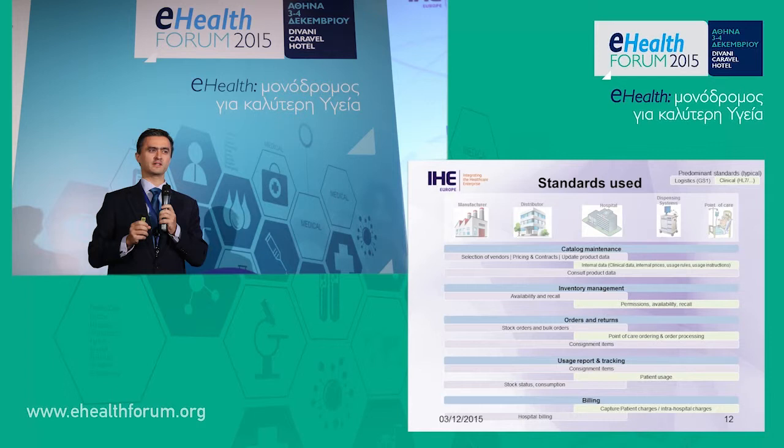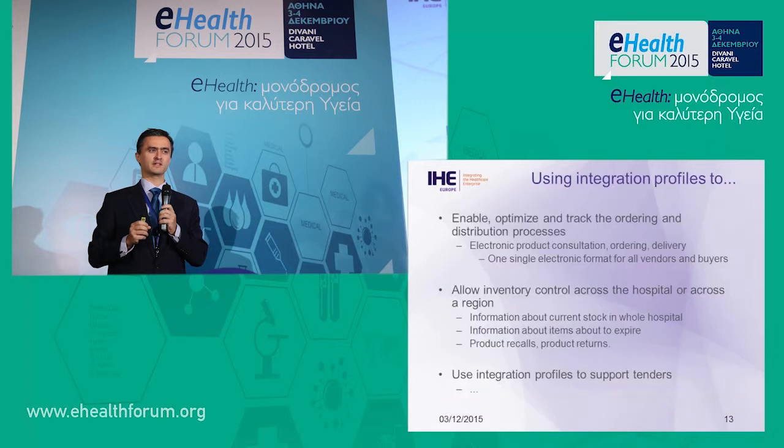if there is a need for checking for adverse events to control a batch, for example, there is a hemodialysis machine that has a problem in one of the filters, what was the patient that first complained about this, and which patients should we call to see if they have the same problem as well, looking at traceability of the machines, where are the devices, and on which patients have they been used. So this is extremely important to follow the full chain, and we use HL7 for that, more inside of the clinical workflows, and GS1 for adopting the universal standard for this.